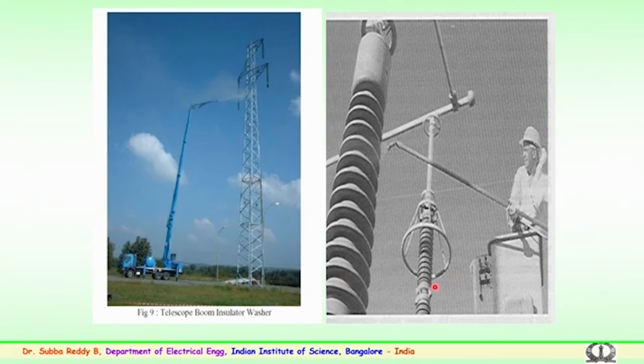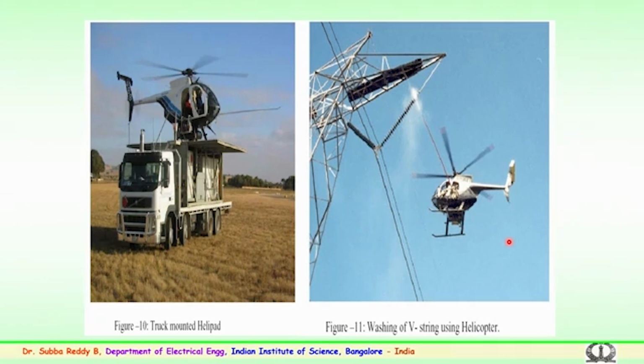So, one is live line washing, which is being shown here in this figure. Live line washing is also very important because you cannot interrupt the supply over a period of time. So, the activity of line washing has to be carried out, which is one of the methods to see that flashover of the substation equipment or the switchgear does not happen during working conditions, particularly during the monsoon. And there are other methods which are being employed for areas like high altitude, mountainous areas, or areas where the vehicle, that is a truck with a jet, could not approach. In such cases helicopter mounted nozzle sets are employed, and with the help of helicopter mounted water jets the cleaning of insulators is done.